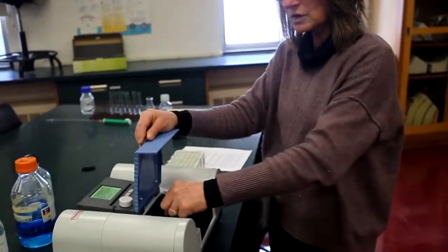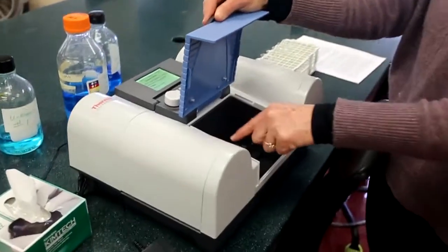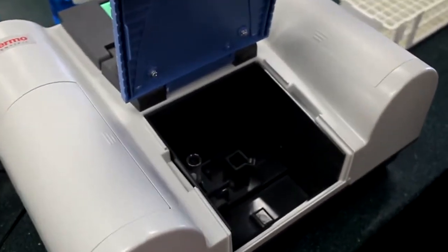So before you start, and every time you change the wavelength on the spectrophotometer, you always want to put a tube of plain water, or whatever makes sense for the experiment or the measurement you're taking, in there, and then you can hit a button called blank, and that will tell the instrument that that's considered no absorbance. So it's important to have that concept. Two things to remember: always make sure your test tube is clean. Always remember it goes in the right compartment in the instrument so that the light beam can go through it properly.